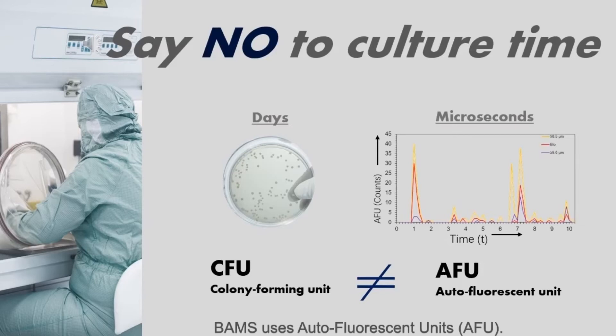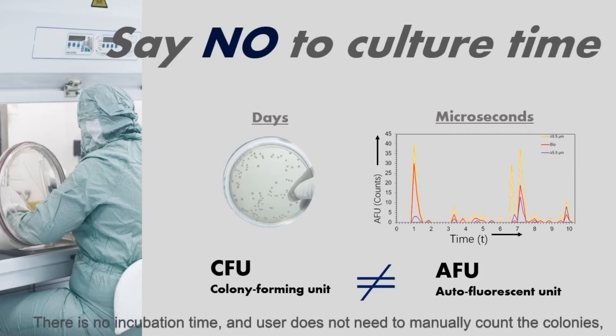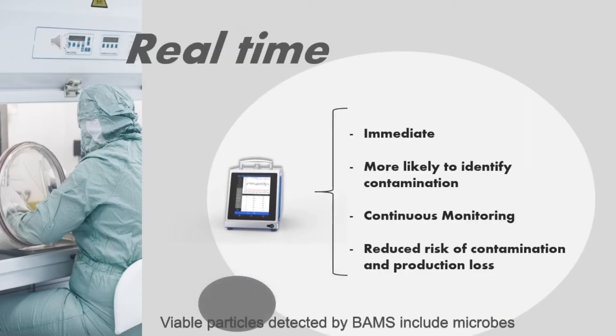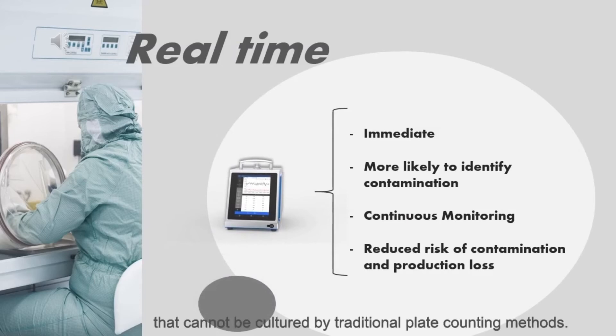BAMS uses autofluorescent units, or AFU. This unit reflects particle size and fluorescence. There is no incubation time and it does not require manually counting colonies. AFU counts are displayed on screen in real time. Viable particles detected by BAMS include microbes that can be cultured by plate-counting methods and also viable but non-culturable particles that cannot be cultured by traditional plate-counting methods.